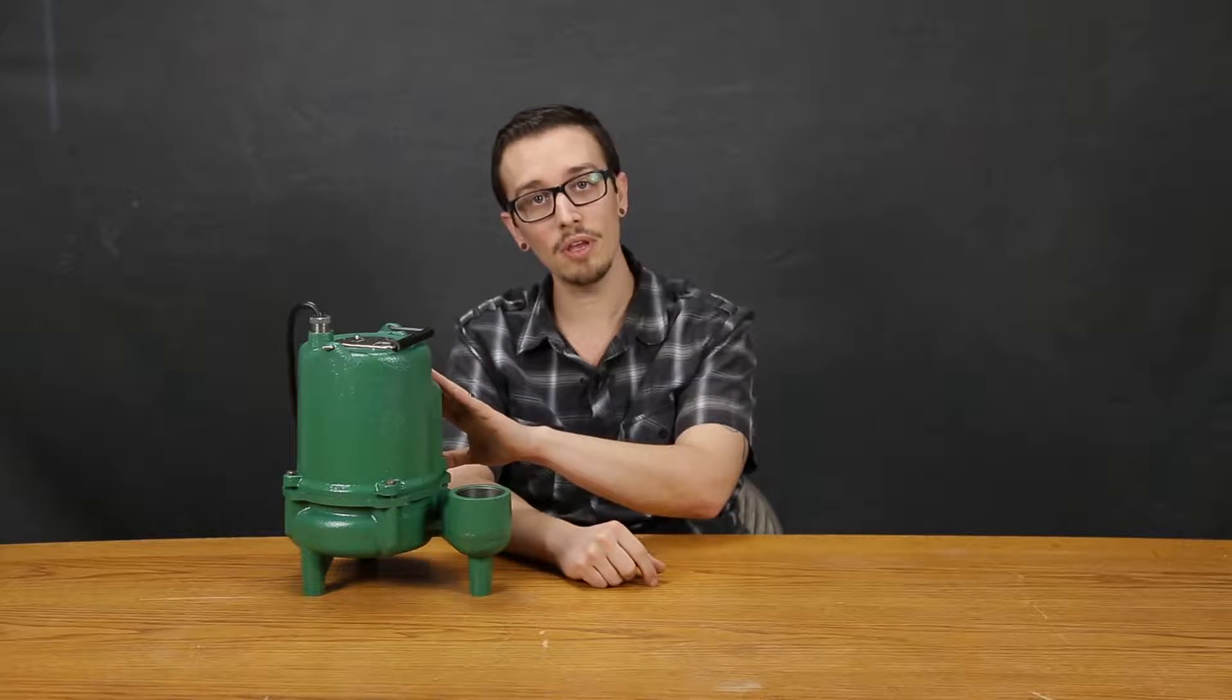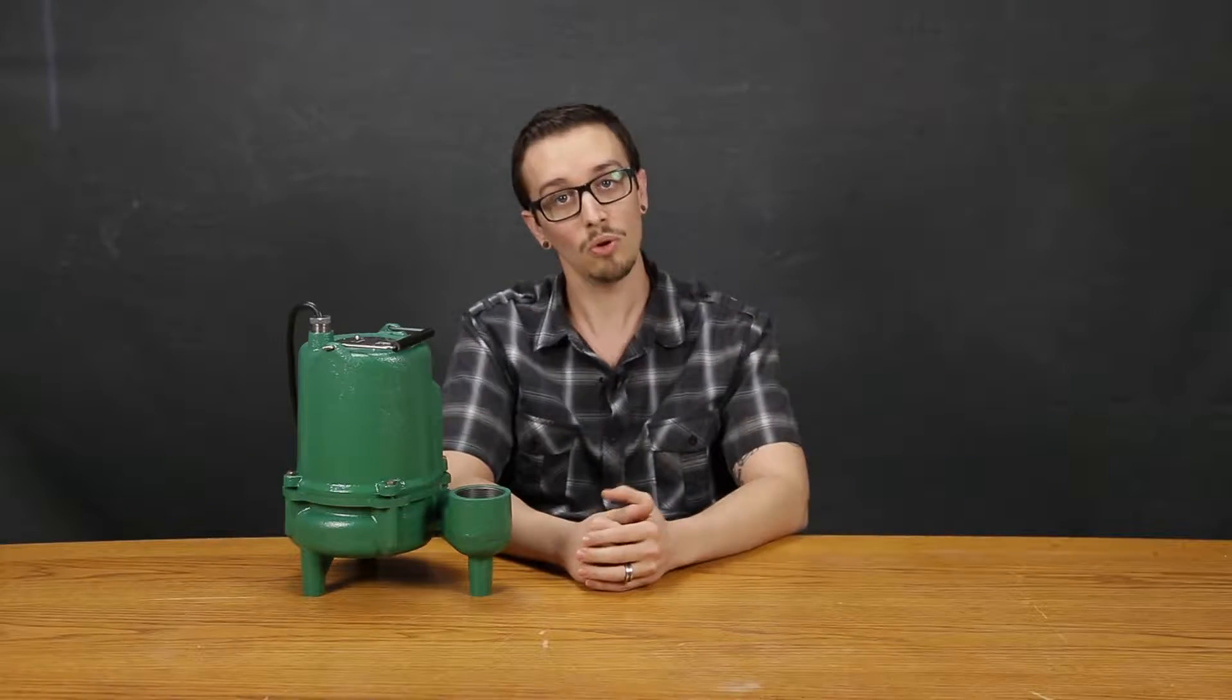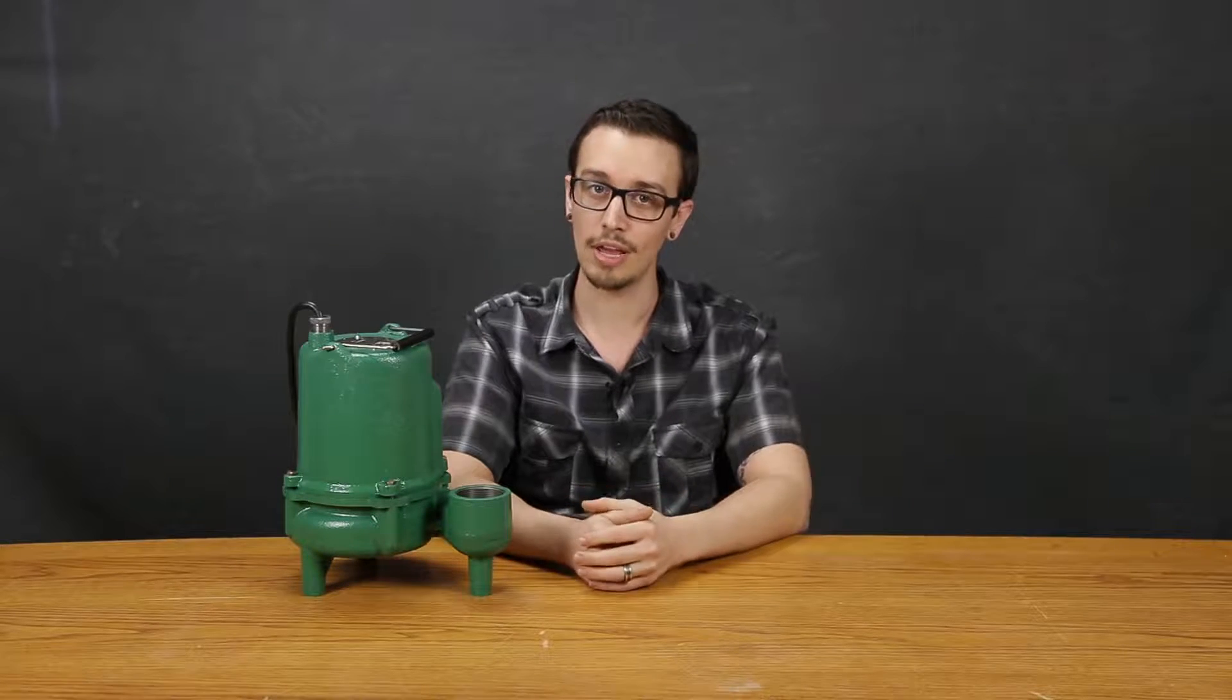The Myers MSP40 boasts a 4 tenths horsepower motor that comes in 115 or 230 volt single phase and is rated for 7.5 or 3.8 full load amps respectively.